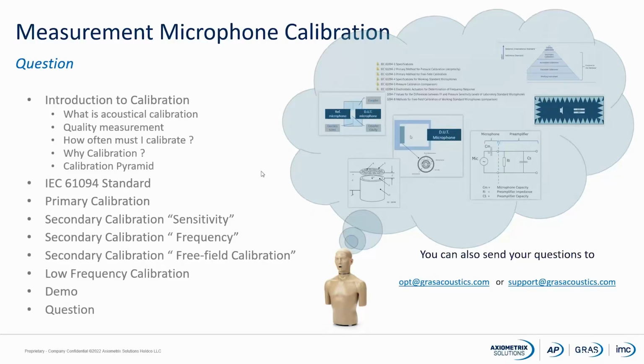Then we have one here. How is the traceability for the test platform performed? When we are selling our 90CA-S2 system, then we will normally sell it together with an accredited calibration. So you have actually a traceability back to a lab here in Denmark. So when we are selling it, then it is actually traceable to DFM, which is the highest authority of calibration in Denmark. So it's a primary lab you have the traceability back to.